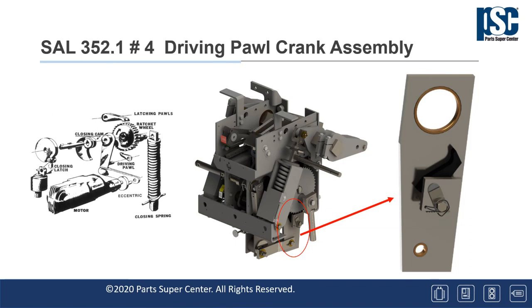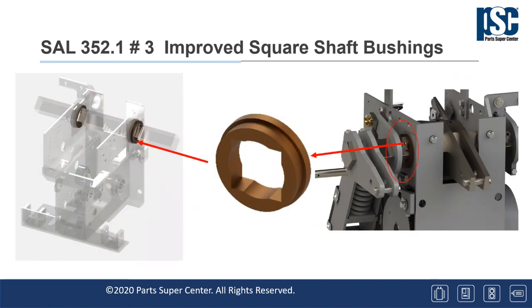Next up is number 3 on SAL 352.1, which standardized on the superior bronze square shaft bushings and eliminated the cast iron bushings that were used on certain ML13 breaker mechanisms. This change was introduced into production on breakers manufactured 1985 and later. This advisory is recommended to be added during the next breaker overhaul.